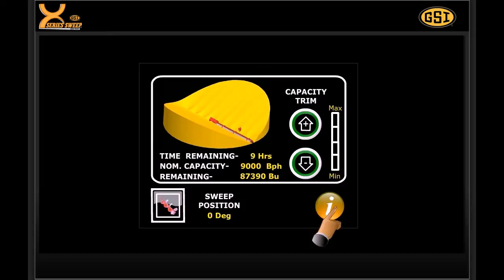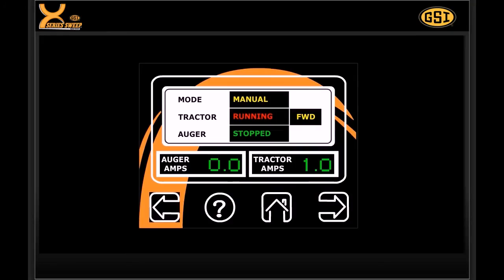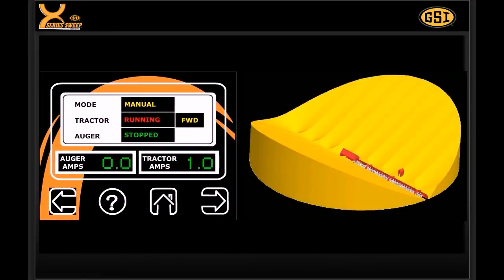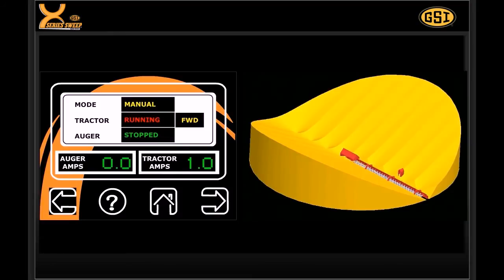The X-Series control senses the amp draw of both the drive and sweep motors to maximize its capacity at preset levels. An integrated sweep position sensor allows the sweep to estimate the number of bushels left in the bin, as well as time remaining to completely sweep the bin.